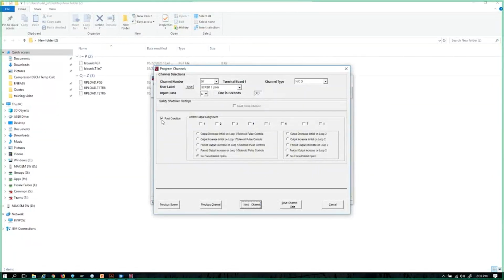There are some cases, and I've worked on many of these cases, where somebody wanted to monitor a discrete channel, so a normally open or normally closed switch, and they didn't want to create a fault, but instead they wanted to turn on a digital output, and that's why this is there for flexibility. I'm just scrolling through the channels.